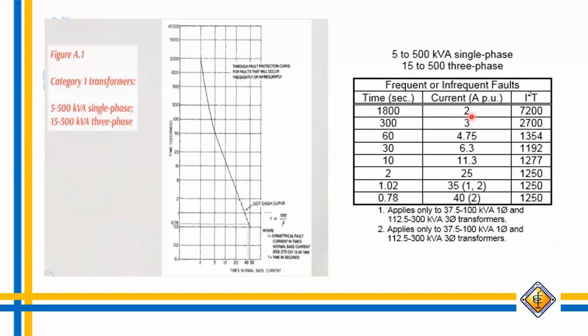Okay? So the current is in per unit, so simply multiply it by the full load current of your transformer, either on the secondary or the primary. But there are considerations there, depending on the winding of your transformer. The delta-Y, for example, the fault on the Y side is different when reflected to the delta. So later, I think I have a figure that will show that.